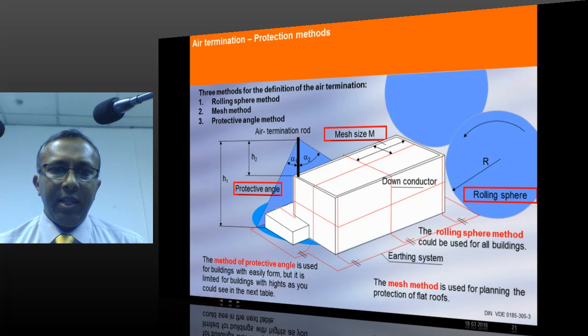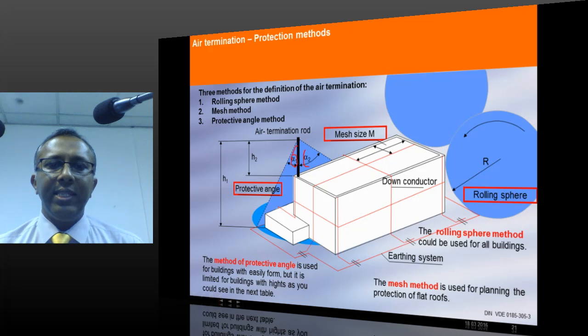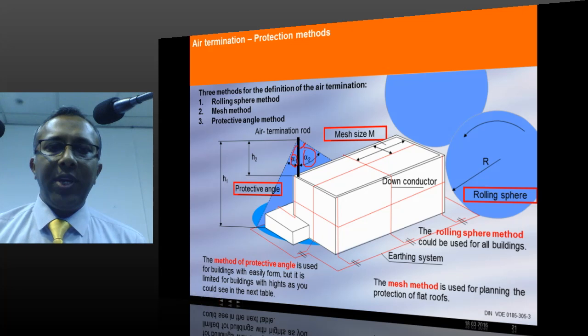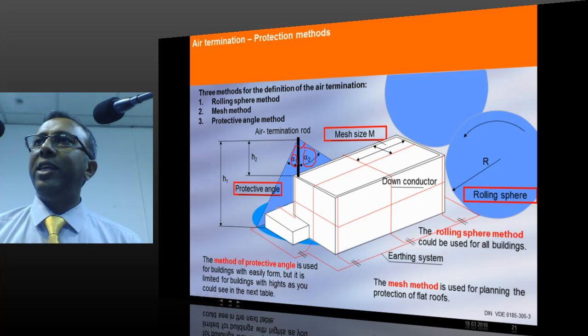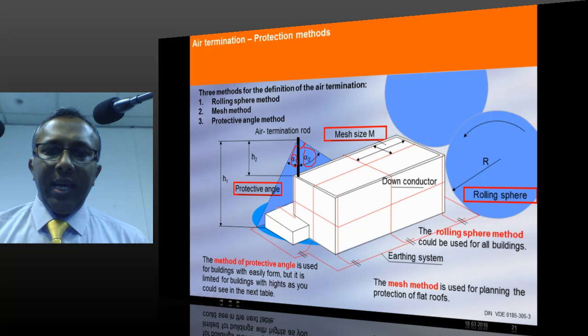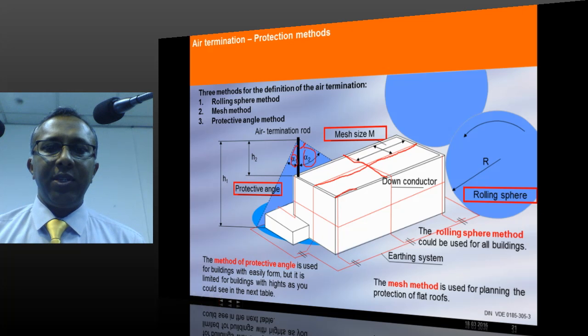See here, a rod which offers this protection, less protection, and the same rod offers a slightly bigger angle of protection. See, this is the bigger angle of protection, because for this part of the building the height we need to consider is less, and for the outside the height we are considering is more. And the mesh method means, you can see at the top of the building there is a mesh, and normally the mesh has to be at this place also.